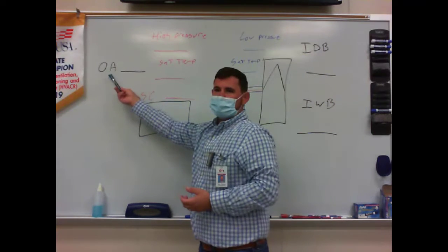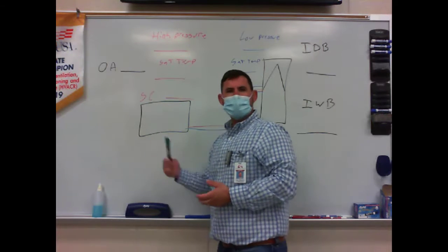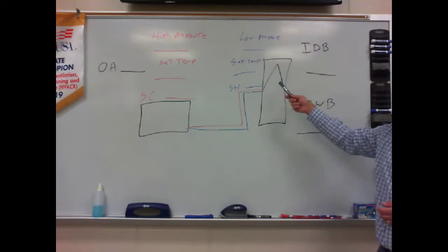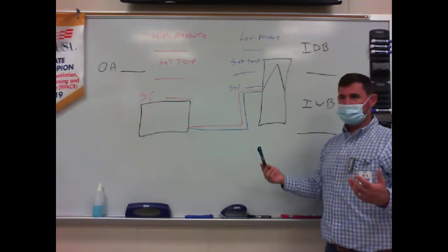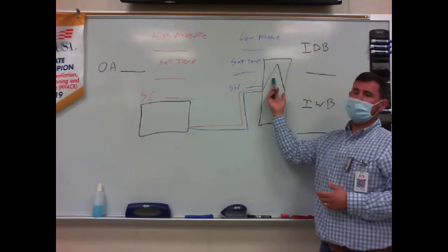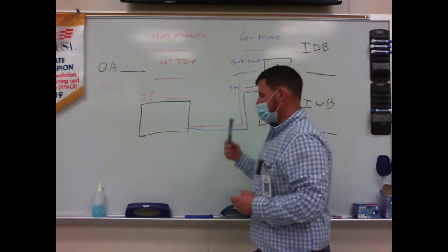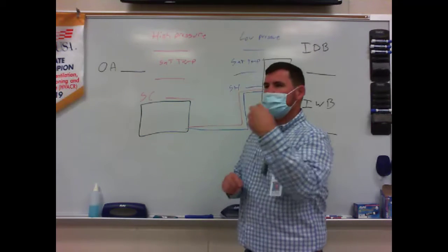It doesn't play a factor on the outdoor unit because all I'm doing is getting rid of sensible heat. But it does play a role on my indoor evaporator because as it's absorbing heat, it's also absorbing humidity as well, dehumidifying the room. So I need to know my total heat load on the evaporator before I can know whether my system's working properly. All right, let's look at some pressures.